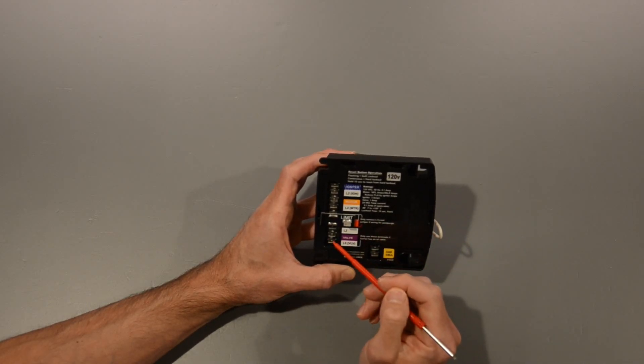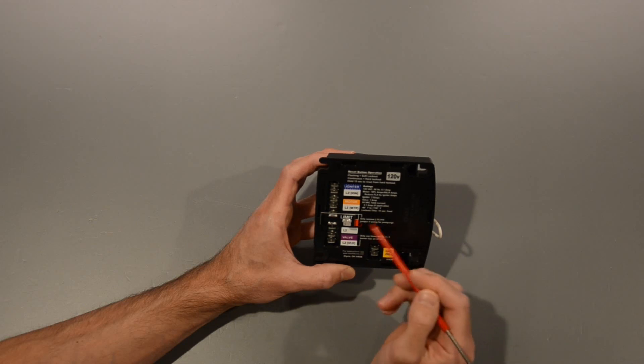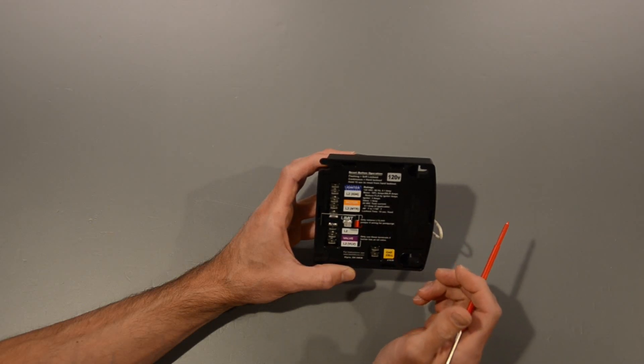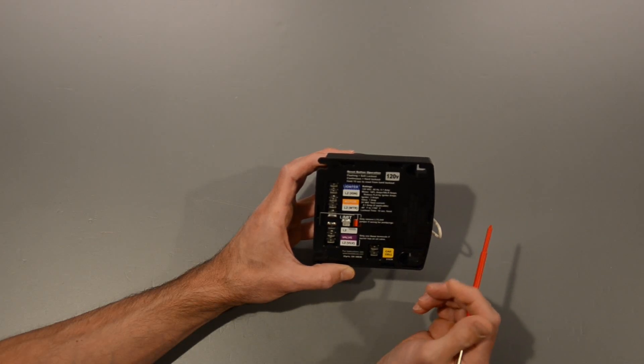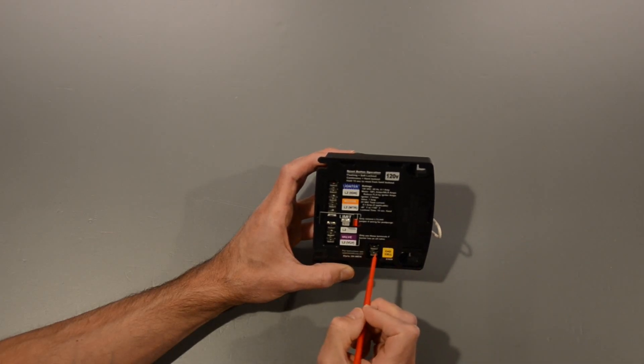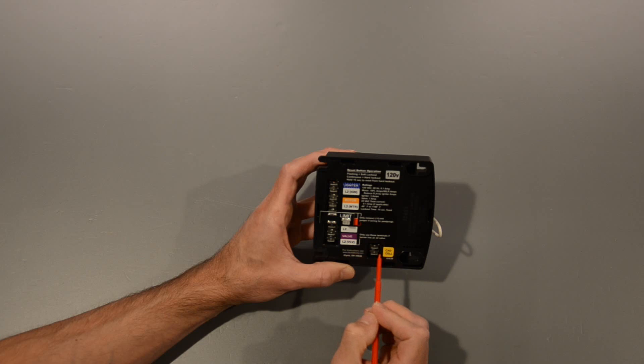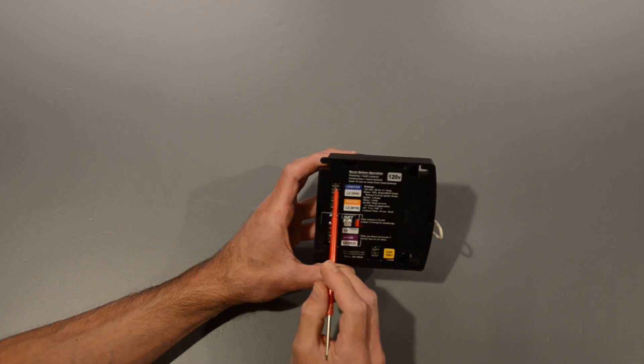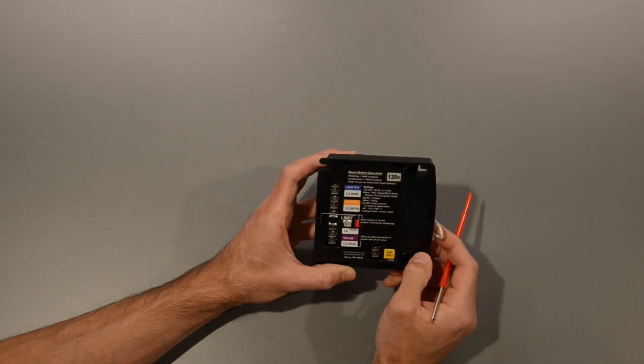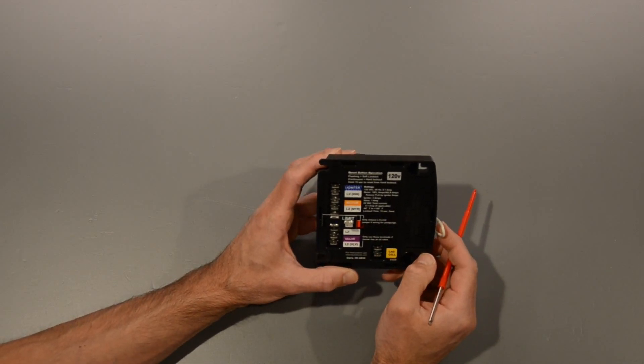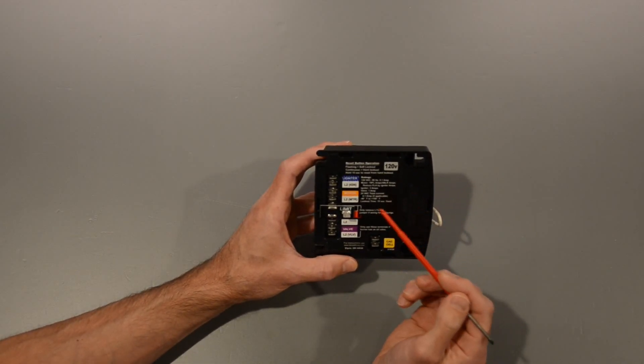After the solenoid valve opens, the controller goes through a trial for ignition period, which usually lasts about 10 seconds. After this 10 second period, the cadmium sulfide cell checks to make sure that there is a flame, and as long as this is detecting light, it will shut off the ignition and allow the burner to run until it hits the high limit, at which point, at least in this system, power would shut off and everything would then be powered off.